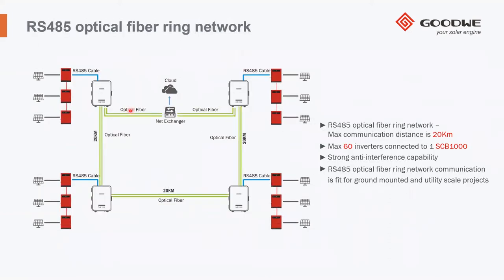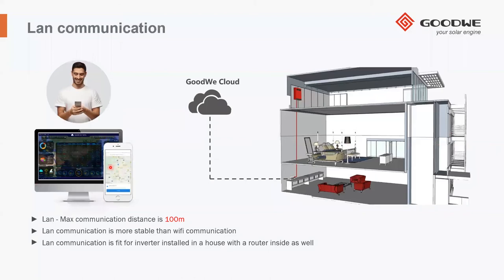Similar to the previous one is the following, where the communication of the data is given through the RS485 cable to the SCB1000, but again the network is made by optical fiber. Again the distance is 20 kilometers, and by using this solution, you can connect up to 60 inverters to one SCB1000. This is the version of the communication box we recommend for this. Another solution which can be implemented is via LAN. In this case, it is via cable, and the communication distance is 100 meters. So as you see, there are very different possibilities, and all of them can be easily implemented in our system.